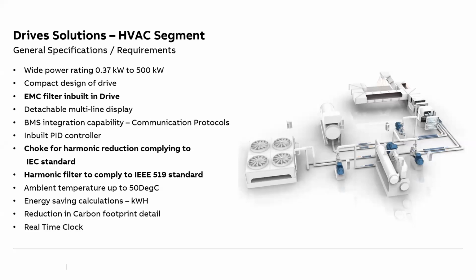Then detachable keypads. Now the keypad is very useful. This is basically the interface or the HMI, where we set all the parameters, do the programming, and where all the data and the various parameters can be viewed. One, it should be an advanced multi-line display, so that multiple data can be visible at the same time. Plus it should be detachable. This is an important feature, because normally if the VFD is mounted inside the panel, there shouldn't be a need to open the panel door every time you have to check any data or make changes in the VFD. The display unit should be detachable from the body of the VFD and suitable to mount on the panel door, so that you can access all the functionality of the VFD from outside without opening the panel door.